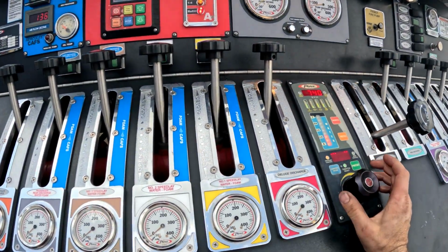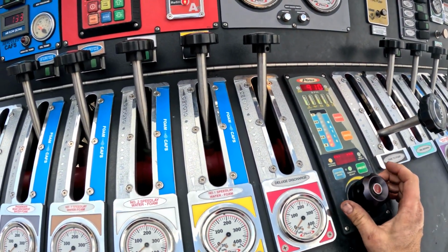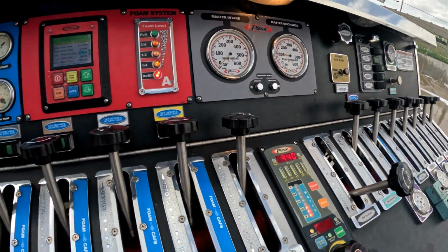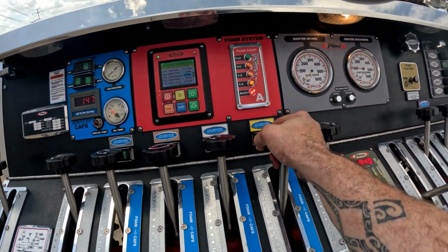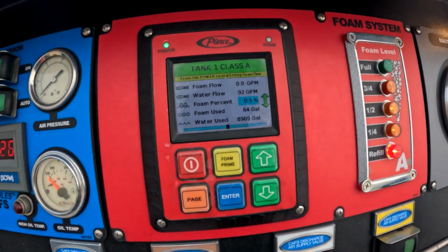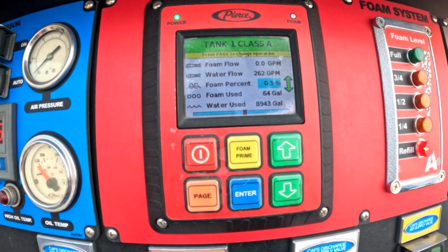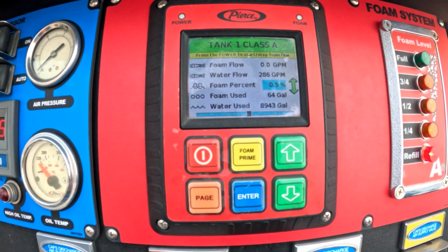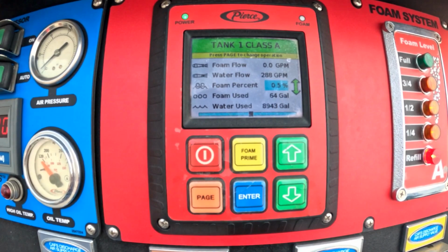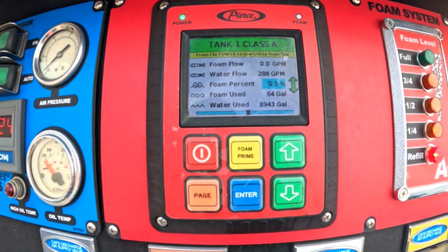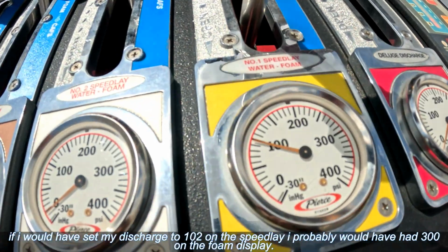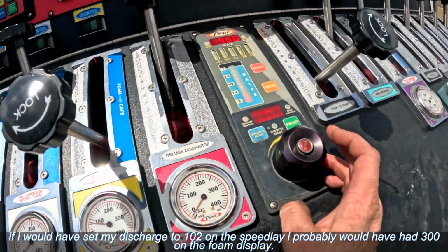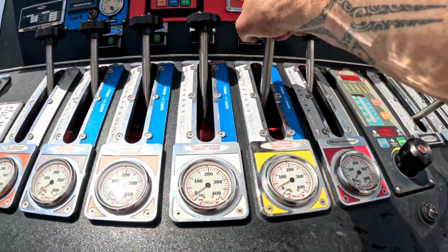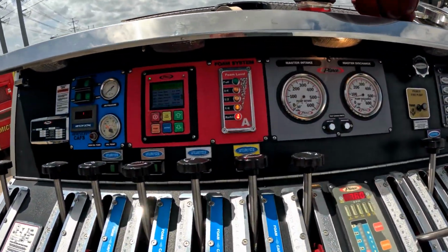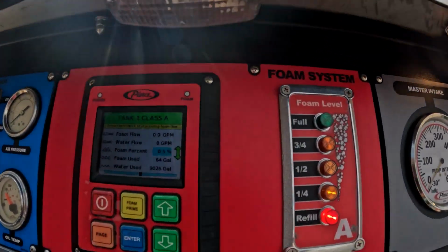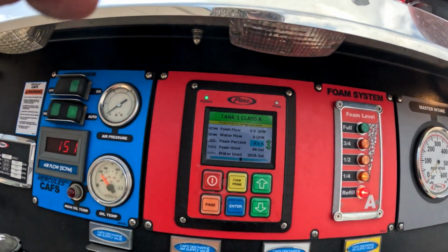Alright, we're gonna dial this up to 102. Do 104 is fine, plus or minus. We'll open her up. And I'm going pretty fast. We're looking for 300 GPM. Pretty damn close. We're not even at 102. So I'm gonna go ahead and shut this down. We're running out of water. I'm gonna close my speed lay. That's it. That's how you verify that you calibrate your water flow meter correctly.